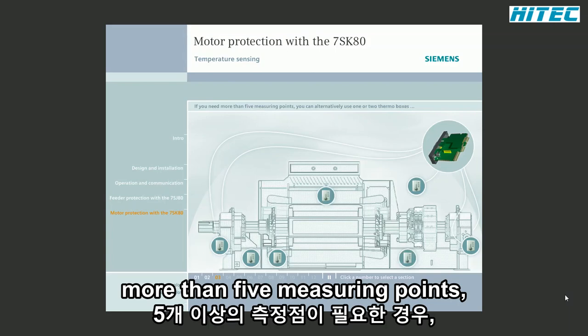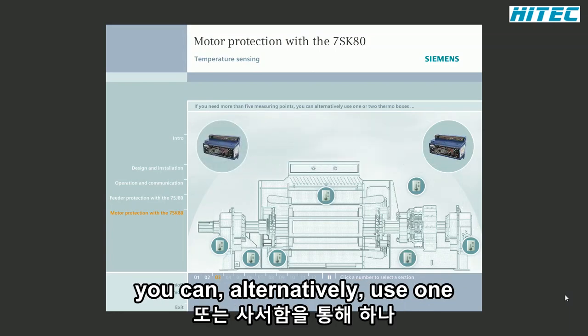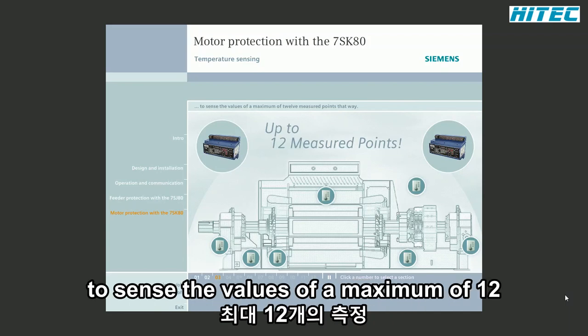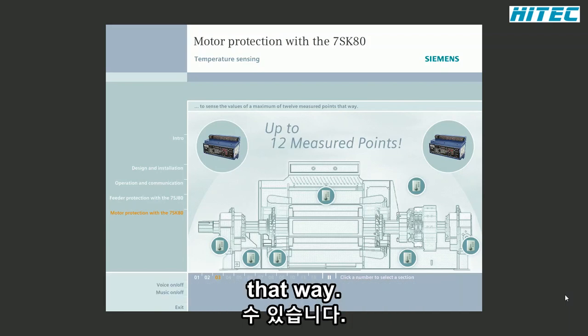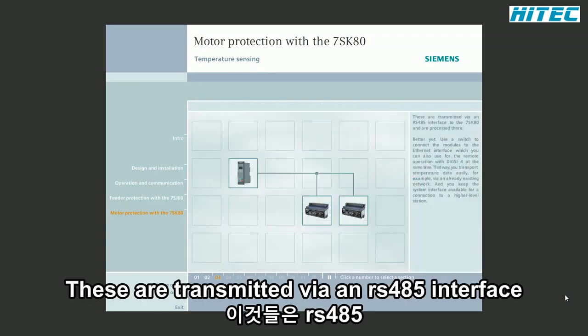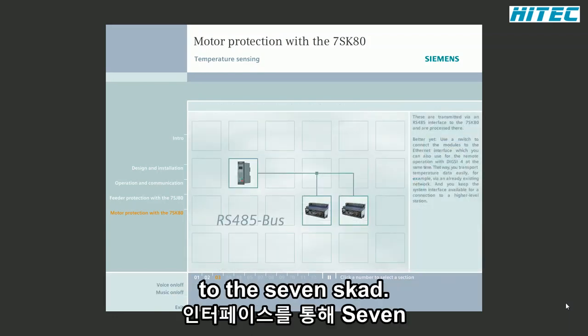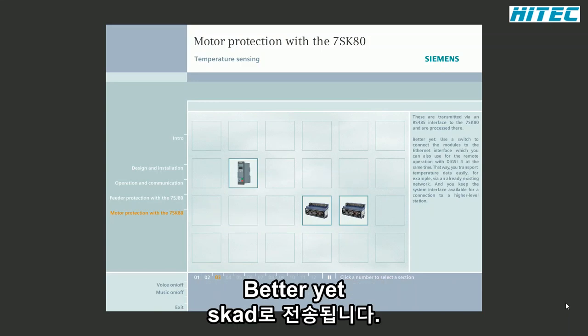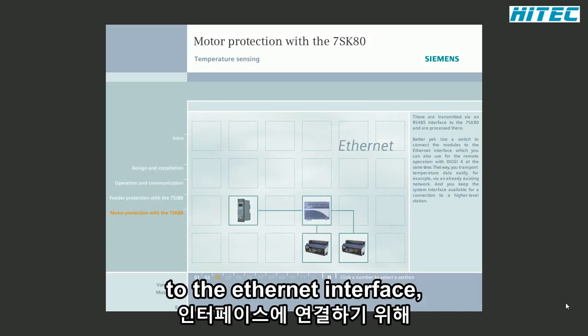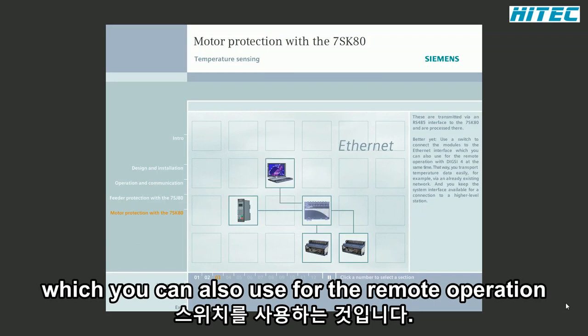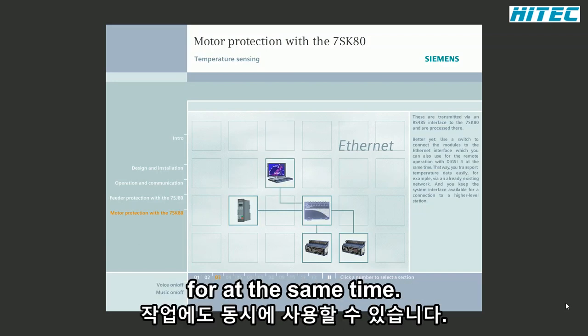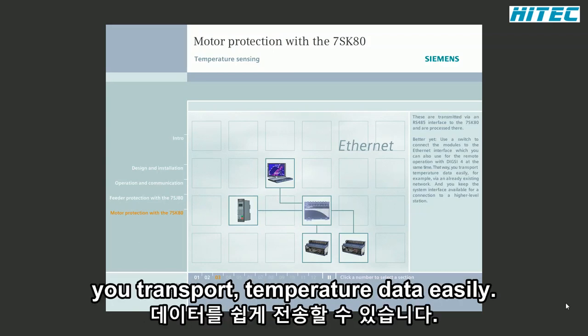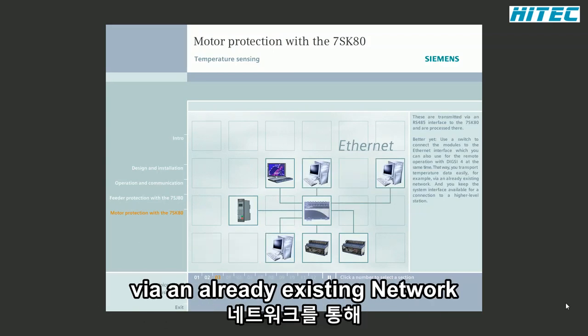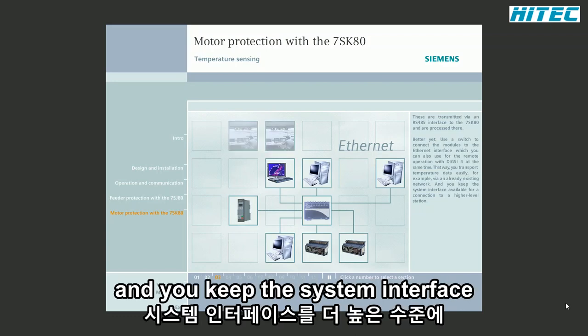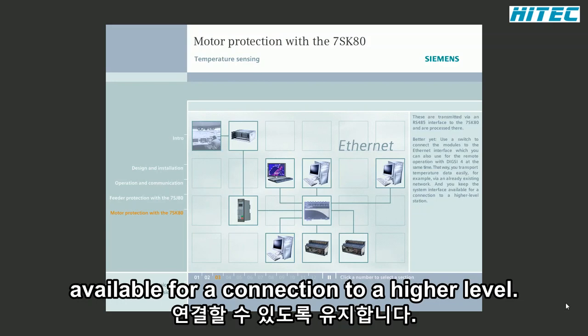If you need more than 5 measuring points, you can alternatively use 1 or 2 thermal boxes to sense the values of a maximum of 12 measured points that way. These are transmitted via an RS485 interface to the 7SK80 and processed there. Better yet, use a switch to connect the modules to the Ethernet interface, which you can also use for the remote operation with DIGSI 4 at the same time. In that way, you transport temperature data easily, for example, via an already existing network. And you keep the system interface available for a connection to a higher level station.